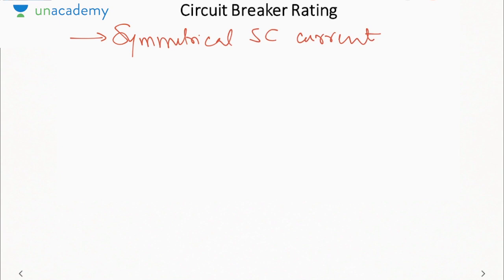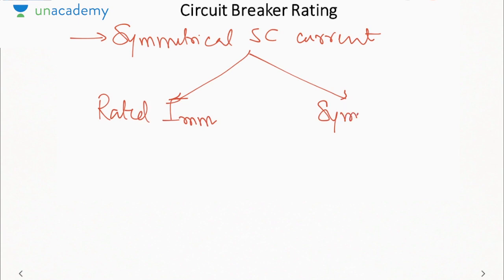Now, what all ratings can be derived from the 3-phase short circuit fault for the selection of circuit breaker? So first, the procedure is to calculate the symmetrical short circuit current. What is a symmetrical short circuit current? That is the AC component of the short circuit current that we were just calculating by using EF and mod Z. That will be your symmetrical short circuit current. Now we define two ratings of a circuit breaker based on this symmetrical short circuit current. One is rated maximum momentary current and the other is symmetrical breaking current, or symmetrical interrupting current.